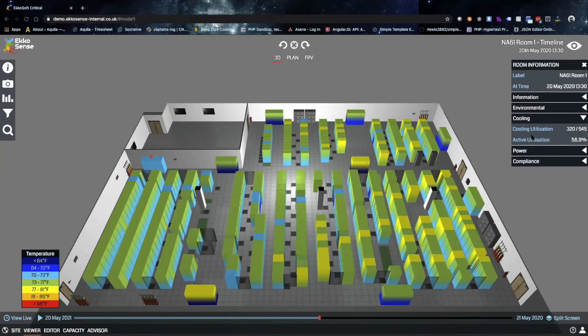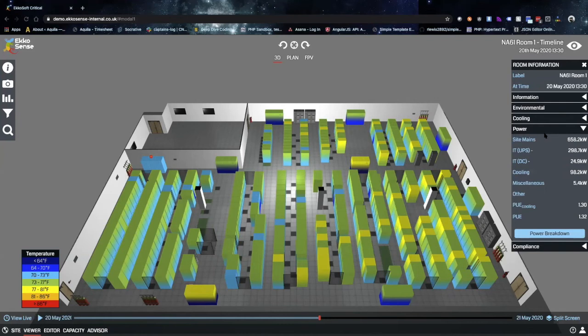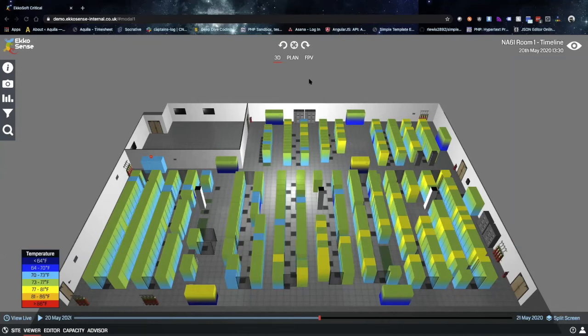Then we can get some more detailed cooling information. So the cooling utilization, so how many kilowatts we're actually using, and then the active utilization percentage. And then we can get some power information. So the site-wide power, the specific UPS and DC power draws right now, the cooling power, and miscellaneous, which is another third-party aspect of the software. So if you're monitoring other types of power that's not IT equipment or AC unit related, that will show up here. And then we can actually look at PUE for cooling as well as total PUE for this room.